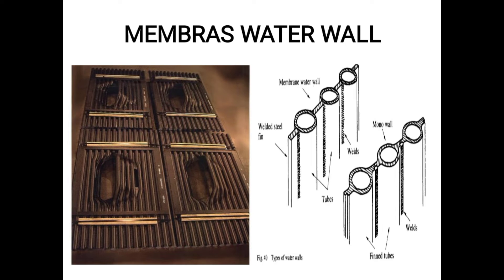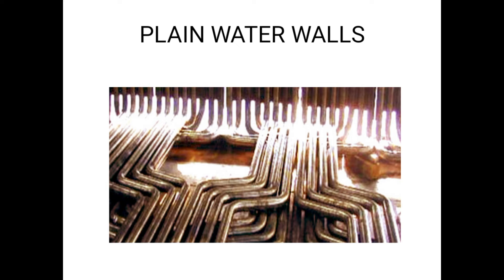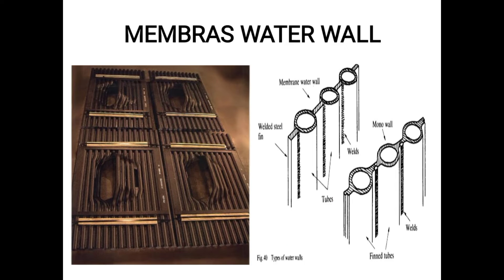Membrane water walls are used in pulverized coal boilers where there is a lot of clinker, where the coal is impure and contains high sludge or foreign particles. In plain water wall tubes there are clear gaps between the tubes, and clinker and dust can get into these spaces. Due to high sulfur content in the fuel, corrosion can occur in these spaces between the tubes.